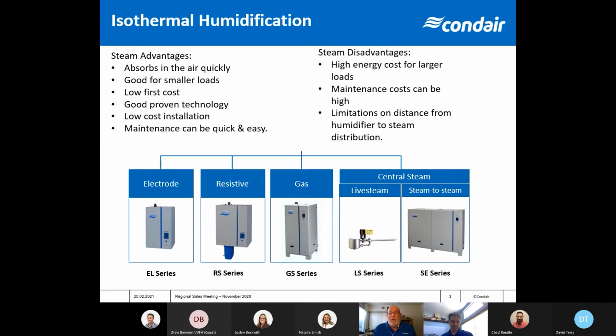You know, if we got 2, 3, 4, 500 pound an hour loads, it takes a lot of electricity to boil a lot of water. Maintenance costs can be high. You know, if you consider replacing cylinders, although there's very little labor involved, there's a bit of material costs. And we have limitations certainly on the distance because it's atmospheric steam, limitations on distance that we can move steam from the humidifier to the duct or the air handling unit. So I use kind of a rule of thumb on that that says I can basically run a steam line 1 equivalent foot per pound per hour capacity of the humidifier up to about 50 feet. So that's kind of my rule of thumb. We can be more precise on the calculation on that, but that's a good guideline.